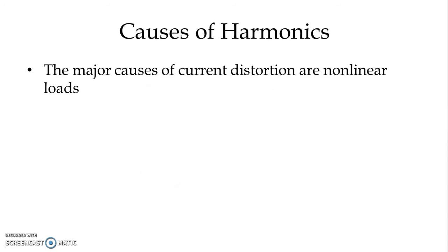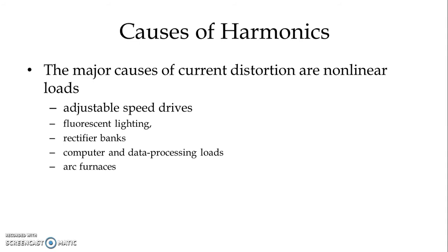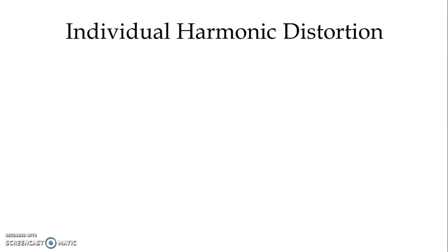Mostly the major causes of current distortion are non-linear loads. For example, adjustable speed drives, fluorescent lighting, rectifier banks, computer and data processing loads, arc furnaces, etc. are a number of non-linear loads which cause very high current distortion. Now let us study individual harmonic distortion.